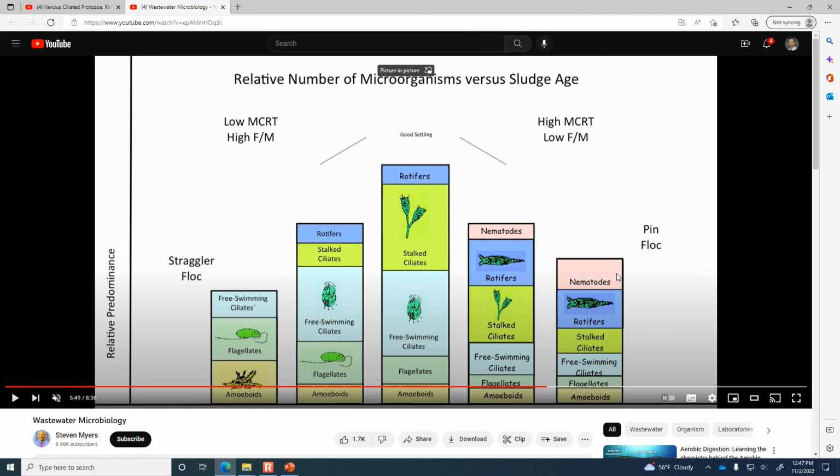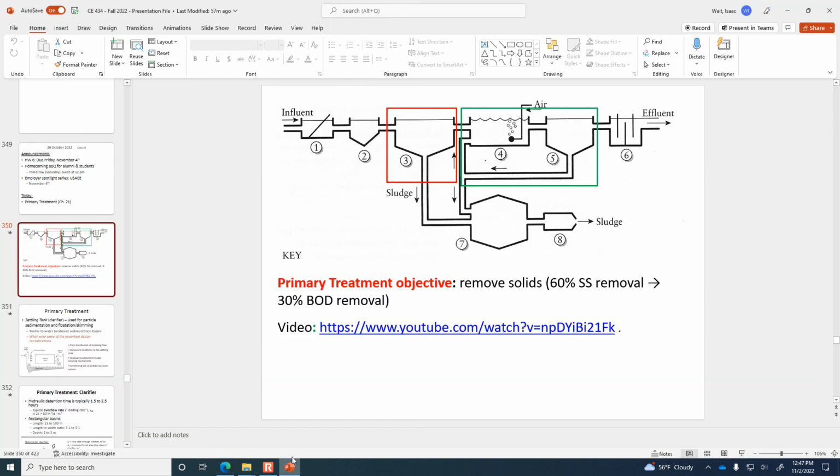And so, the balance between eukaryotes, prokaryotes, rotifers, and so on: typically, microorganism populations that are somewhere in the middle are the most productive in removing BOD quickly and the most resistant to variations in operating changes. So another thing these population studies can tell you is whether you're achieving the right balance of wasting sludge versus recirculating sludge.